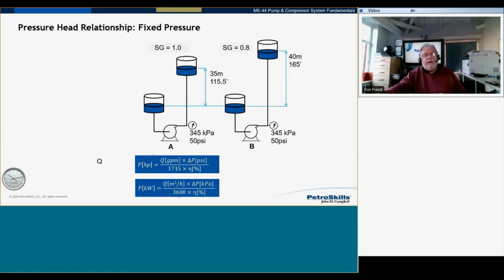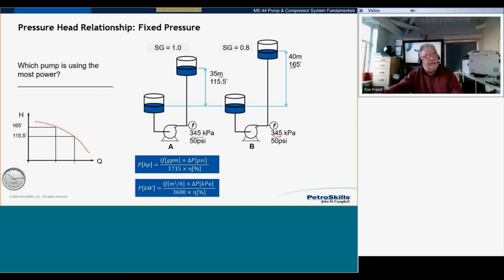What we now have are two pumps delivering the same pressure but different heads. Interesting now. My question is a little bit different. Which pump's using the most power? Tick for pump A, cross for pump B. And I'm not going to make you go through all this again, because it's the same. The flows are going to be different. But if you look at this formula here, power is flow in gallons per minute multiplied by the differential pressure, and then we've got some unit conversions under there. Don't forget the pump efficiency. So the power that the pump needs to move this liquid is flow times differential pressure.